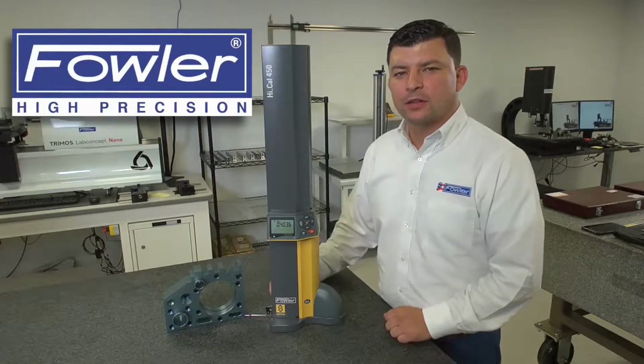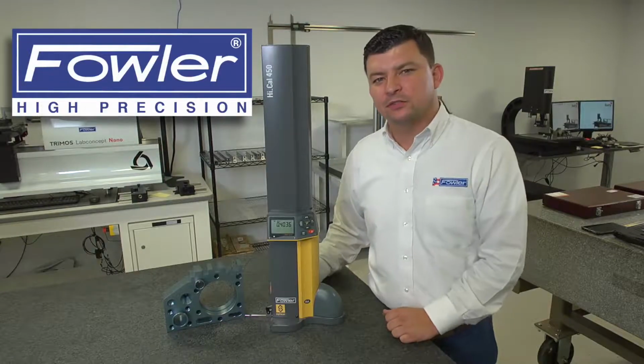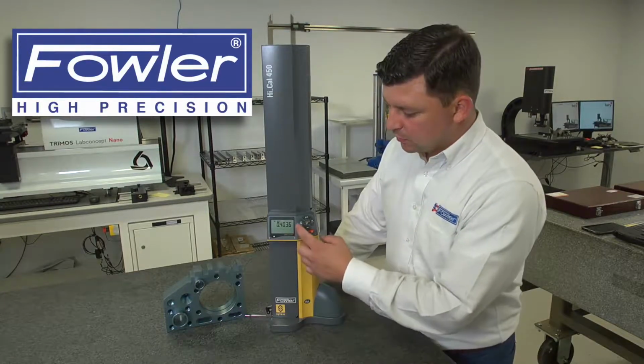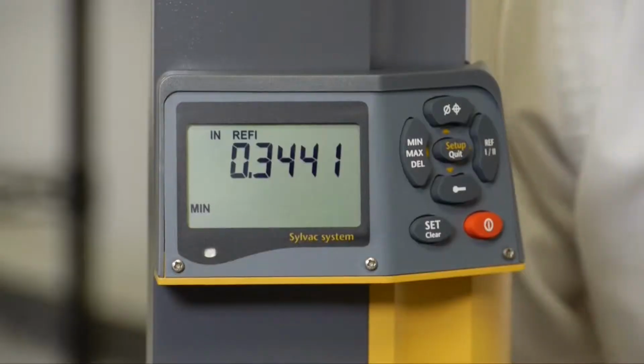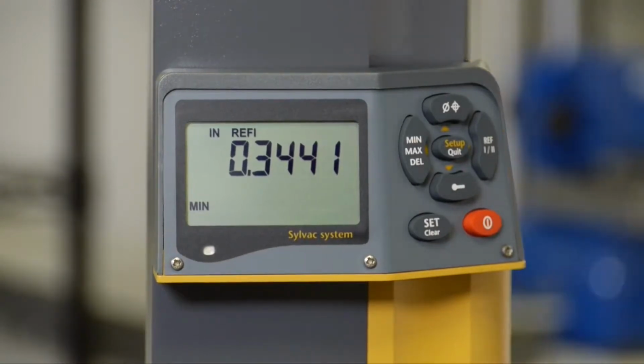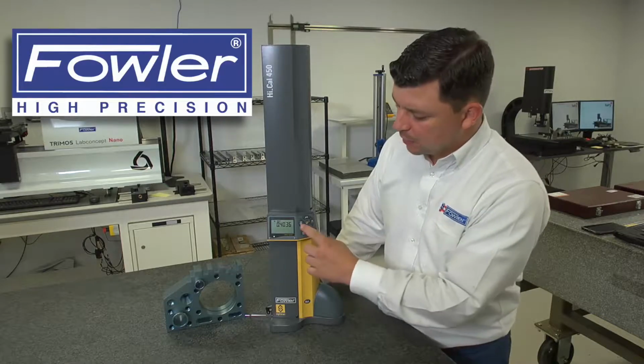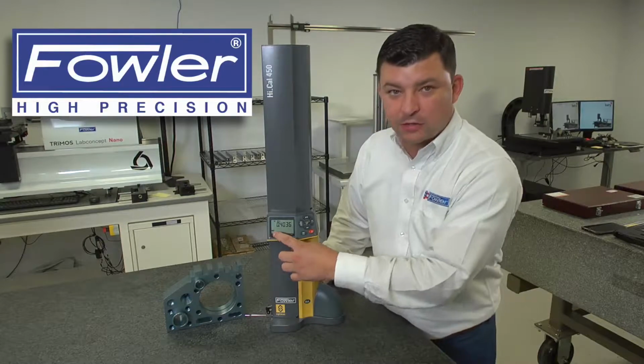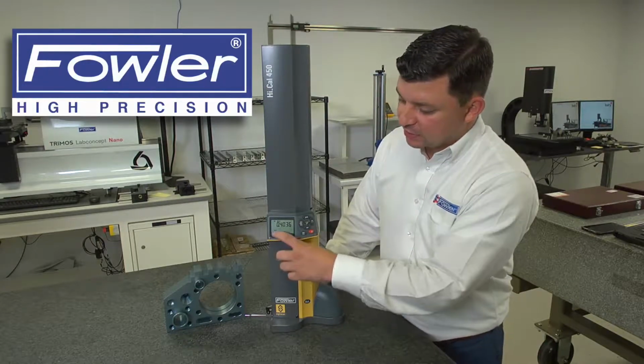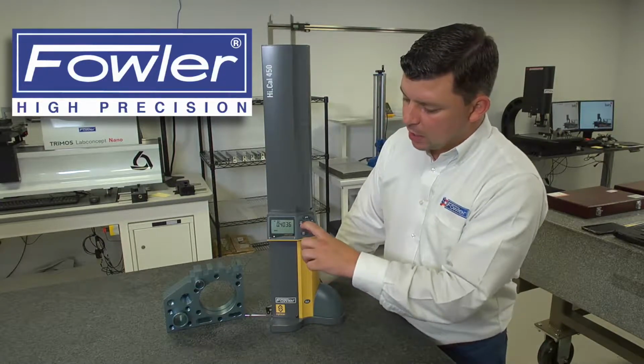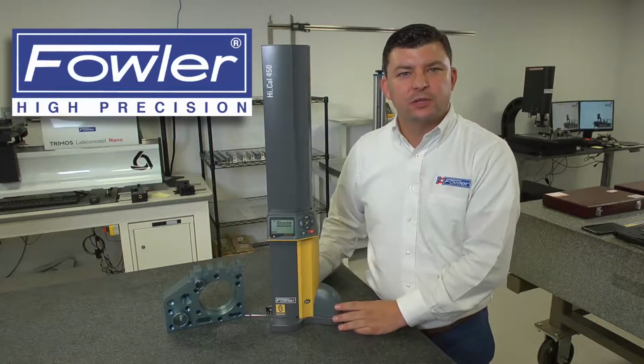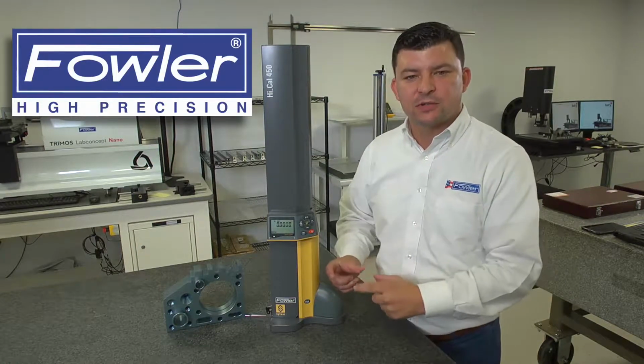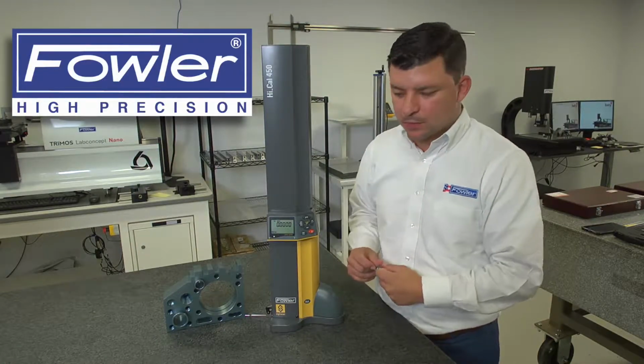In this video, we're going to look at the min-max delta function of the Sylvac Hi-Cal. The min-max button can be located on the left-hand side of the keypad, labeled with min, max, and delta. The first time you hit that button, we enter minimum mode. The second time we enter maximum mode. The third time we enter delta mode, delta being a TIR, the difference between the min and the max.